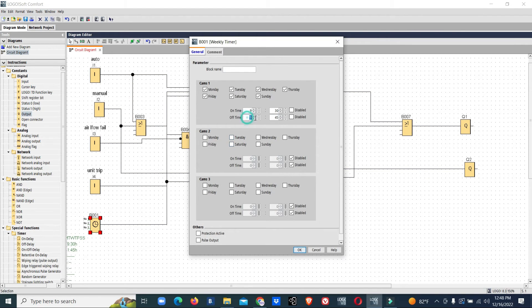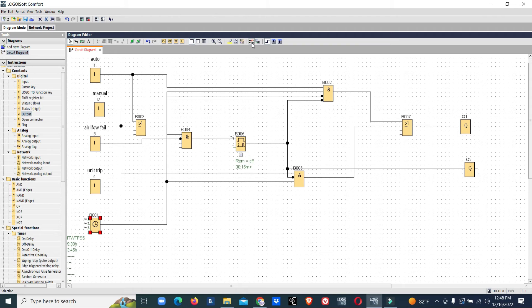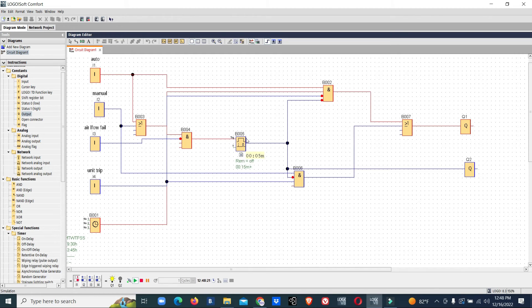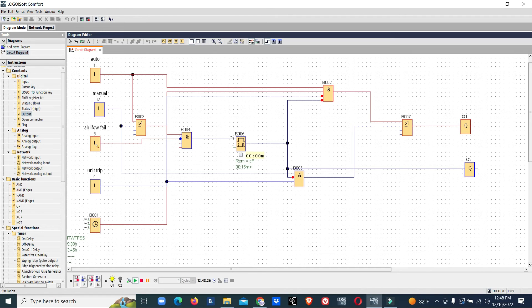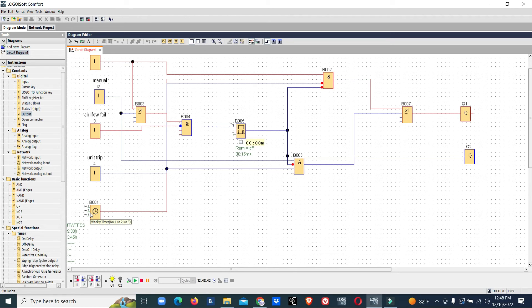Now we will check the simulation. First, we'll start auto mode. The time must be... it's 11:23 now. That was a small misunderstanding. Now we start auto mode. Auto mode has started. At the same time, the airflow fail timer also started. Within the time we will give the input. Now the air is flowing through the duct. The FAHU is running and feeding air to the duct.